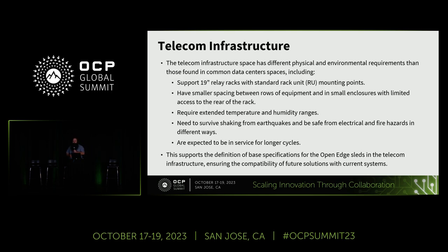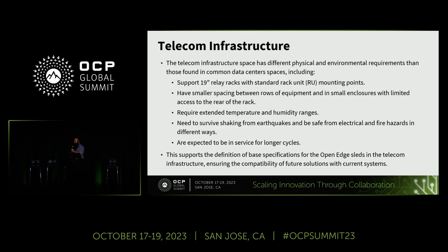In these environments, you may also have limited access to the rear of the rack, so there are strong requirements to have things front-serviceable. There's also a need for extended temperature range and humidity range capabilities — requirements that go beyond traditional data center deployment. Coming from the classic NEBS environment, earthquake and seismic shaking tolerance is required, depending on where these things could be. The goal is they could be hard to service and access. There's also a requirement that these things have a long service life cycle. Doing a truck roll out to these environments may not be easy, so you want something that can withstand environmental extremes and provide high availability.